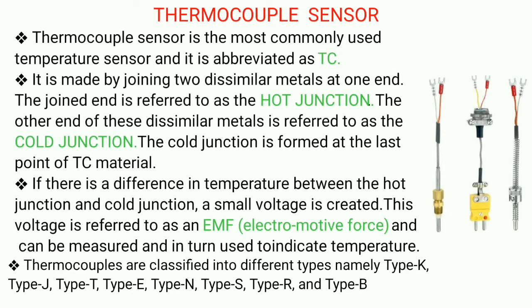Next temperature sensor is a thermocouple. It is a very commonly used temperature sensor. It is made by joining two dissimilar metals. One end is called the hot junction and the other end is called the cold junction or the reference end. It produces a temperature dependent voltage as a result of thermoelectric effect.